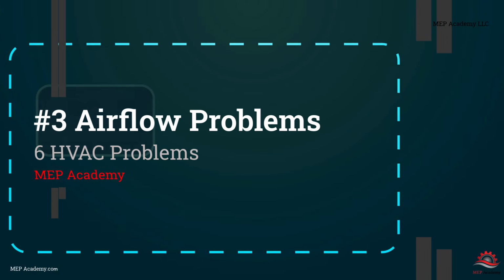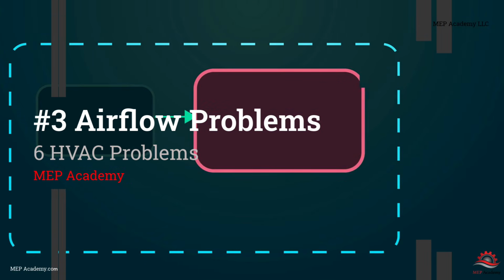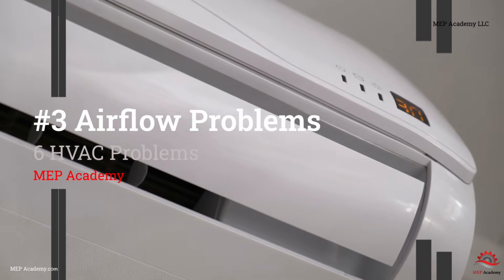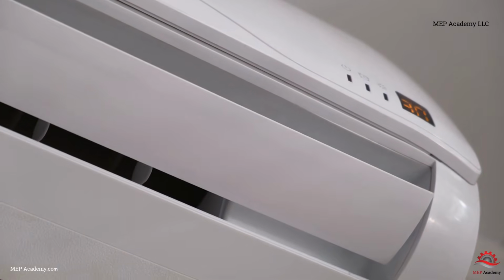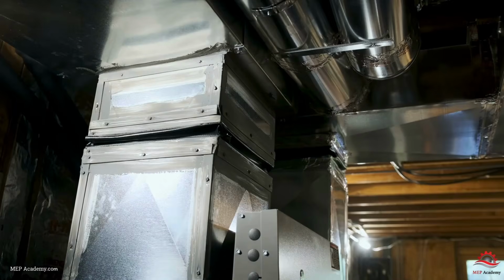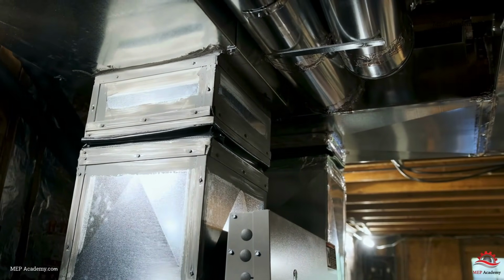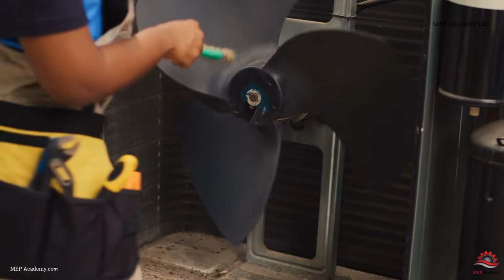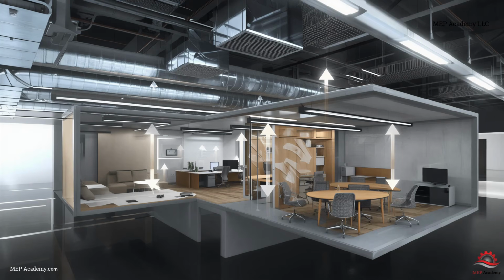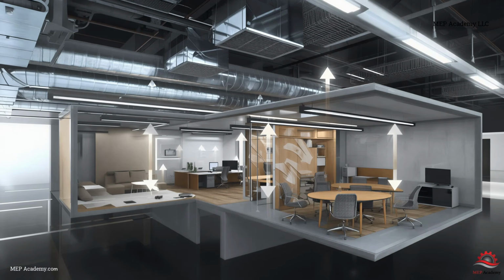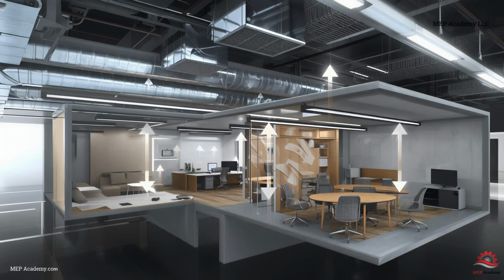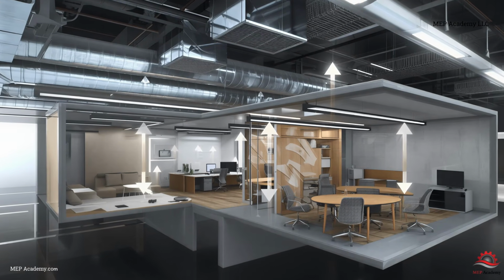Many cooling complaints have nothing to do with refrigeration. The real issue is airflow. The HVAC system may be producing cold air, but that air is not reaching the occupied space in sufficient quantities. Airflow problems can result from undersized ductwork, dirty filters, blocked coils, closed dampers, collapsed flexible duct, leaky ducts, improperly adjusted VAV boxes, fan issues, or excessive static pressure.